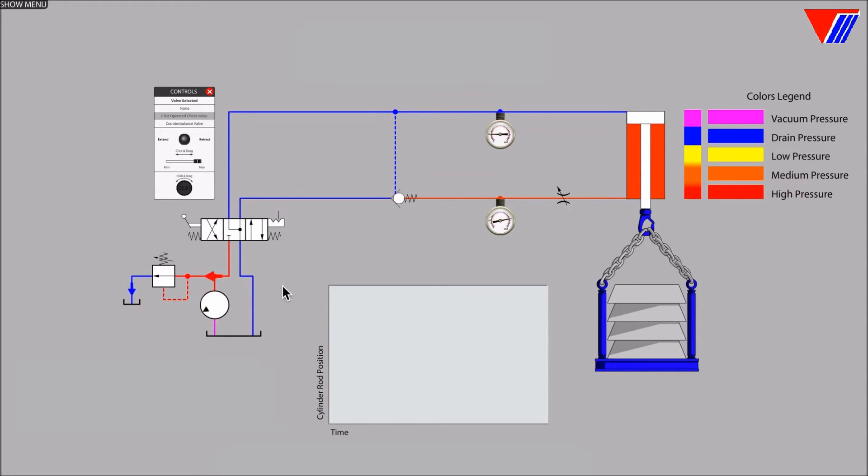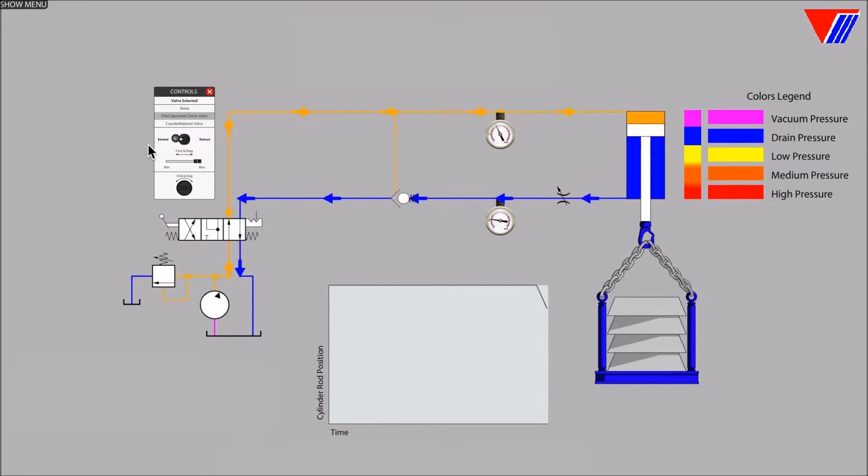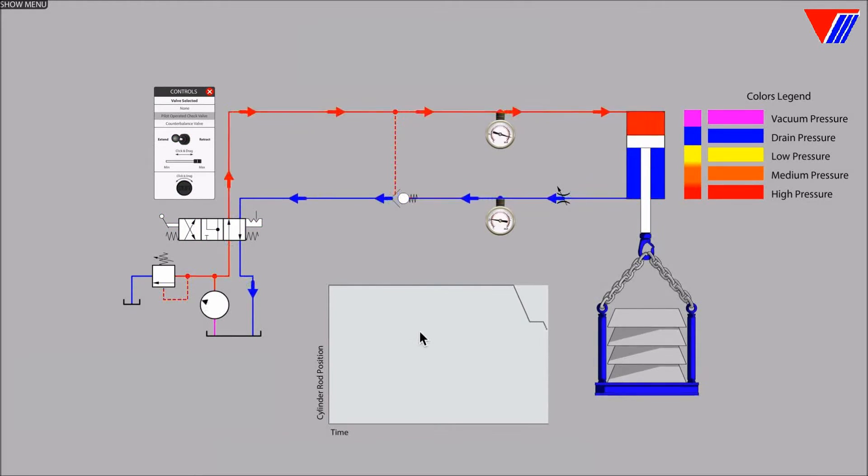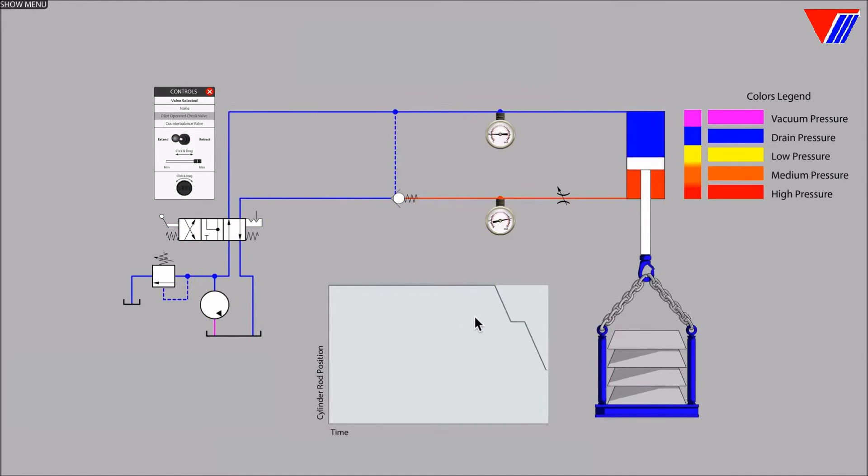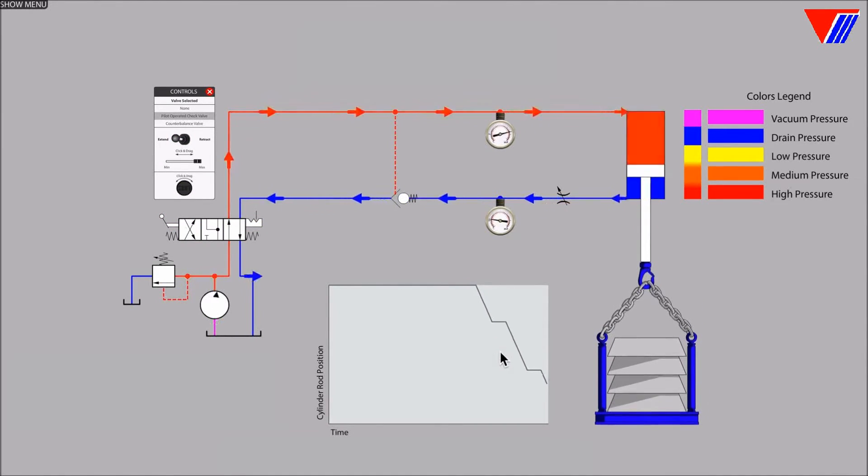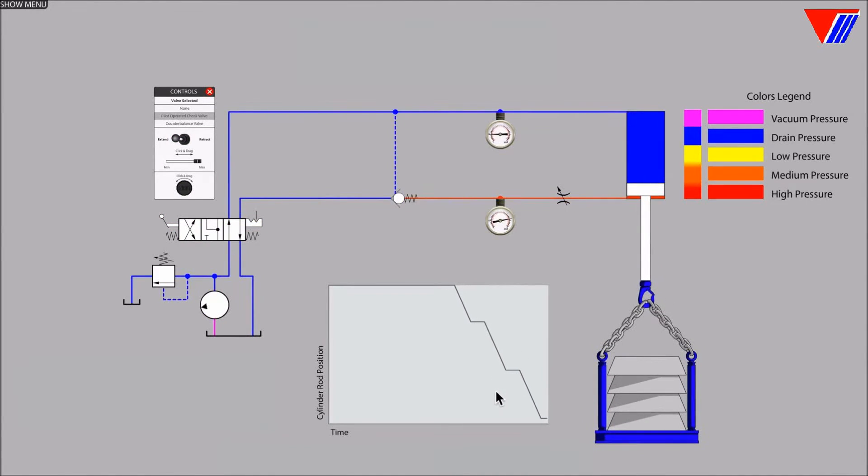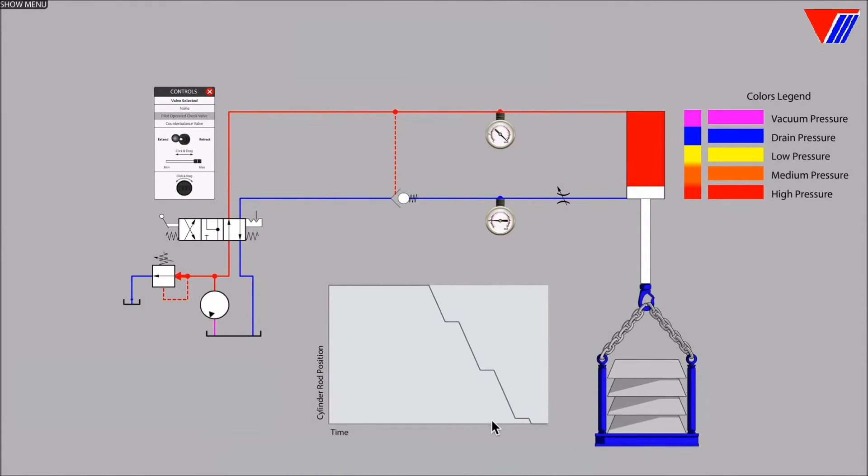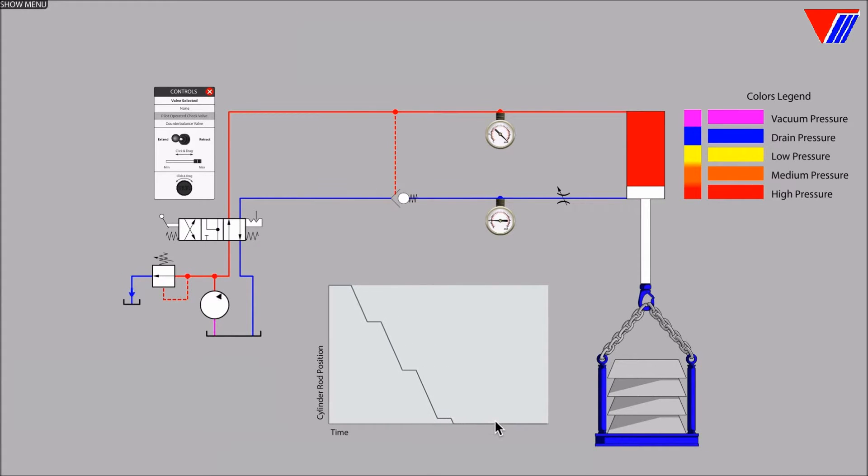Now let's operate the directional valve to lower the load. The check valve opened and slammed shut several times during the lowering of the load creating a very uneven cylinder motion.